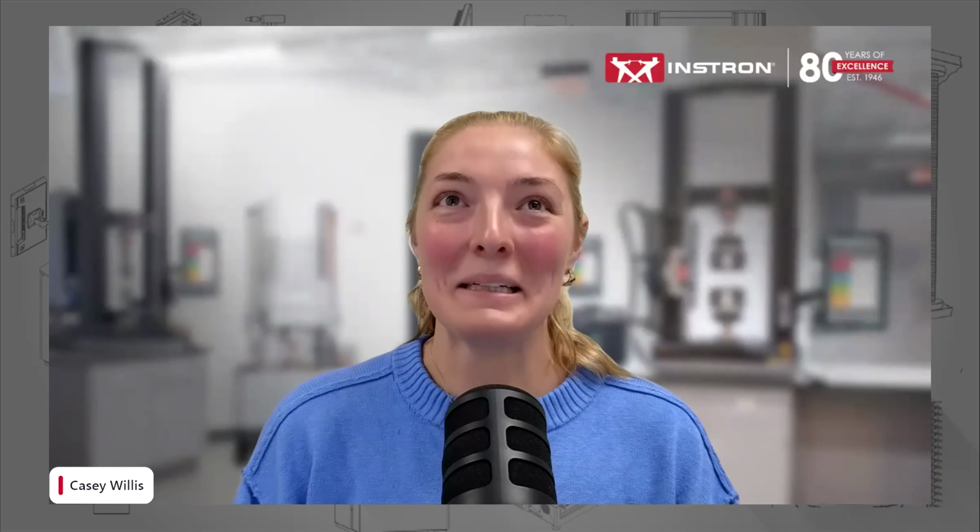So try those things and definitely reach out if you're struggling with anything specific, because our applications team deals with this all the time. Yeah, I'll just echo what Casey said. We definitely have experienced that. What looks best to the eye is not necessarily what will give you the best tracking of the marker with the AVE3. I've had to put white dots on things where black definitely looked like the right choice, but white would give me a much better data signal. Yeah. That's usually from customers testing metallic materials. That's something they learn very quickly.